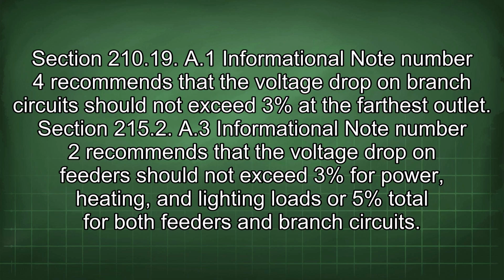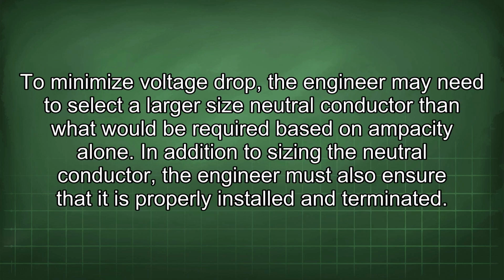Section 210.19(A)(1), Informational Note No. 4 recommends that the voltage drop on branch circuits should not exceed 3% at the farthest outlet. Section 215.2(A)(3), Informational Note No. 2 recommends that the voltage drop on feeders should not exceed 3% for power, heating, and lighting loads or 5% total for both feeders and branch circuits. To minimize voltage drop, the engineer may need to select a larger size neutral conductor than what would be required based on ampacity alone.